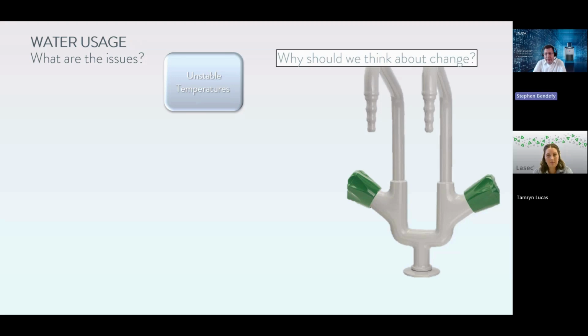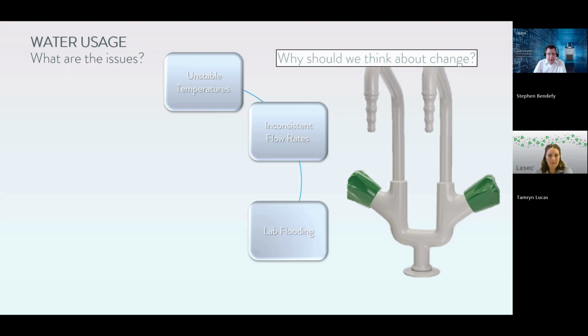Unstable temperatures, inconsistent flow rates. If the flow rate is constantly changing, then the level of cooling that's being applied to a condenser will change. Why would a flow rate change? Well, perhaps there's other demand on the system. Maybe there's a machine nearby that is also using that water supply, and as the demand for that machine increases or decreases, then the flow rate changes. It could also change the pressure in the system. By changing the pressure, you may find that there's a back pressure on the tubes.